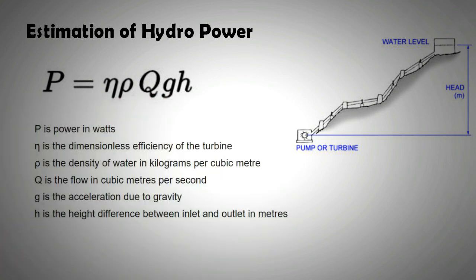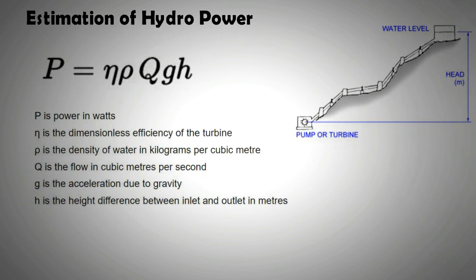Eta is the dimensionless efficiency of the turbine. For Francis and Kaplan turbines it's nearly 92 percent. Rho is the density of water in kg per meter cube. Q is the flow rate in cubic meters per second. G is the acceleration due to gravity and h is the height difference between the inlet and the outlet in meters.